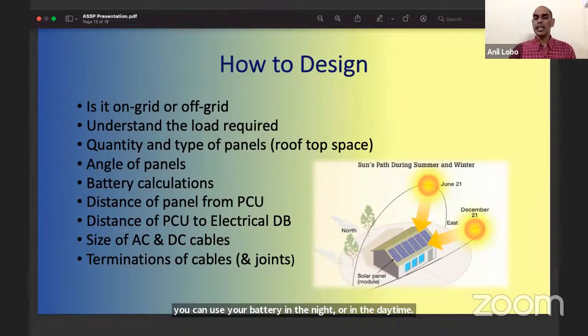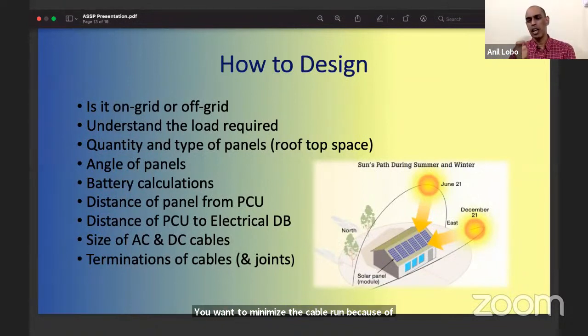Two other criteria that you have to look at is the distance from the solar panel to the PCU. Now remember, the solar panel sitting on the roof is running down to your power conditioning unit on a DC cable. You want to minimize the cable run because of loss of energy. The loss of energy in DC systems is much higher than in AC systems. So you want to keep your solar inverter as close as practically possible to the solar panel.